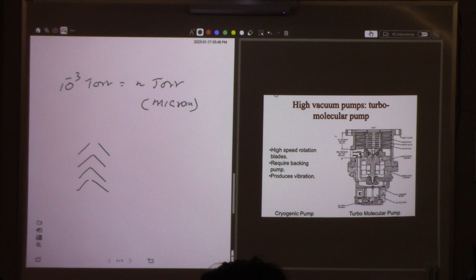What happens is, when you rotate these, the gas molecules, since this is connected to the chamber, right, will be ejected because of the very high speed. These blades rotating at very high speed again transfer momentum to the gas molecules. Diffusion pump transfers momentum from those oil streams. Here momentum transfers directly from the high-speed blades, right? So that rotational kinetic energy sends them out of the exhaust.